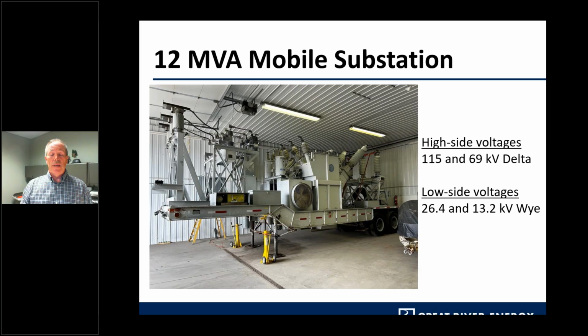And then from there we can connect to our regulator trailer, and then finally to the distribution substation. These mobiles are here as co-ops continue to improve their backfeeding infrastructure, so emergency demand has gotten less in recent years, but it's still a critical part of our resiliency and keeping all our members energized and online. The other thing we have used the mobile sub for is to prevent overloading depending on weather and conditions, and if there's been a certain line outage, so our members' transformer isn't overloaded, we will put in a mobile to help with a backfeed situation to prevent overloading of their distribution lines.